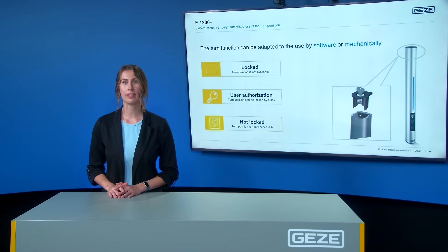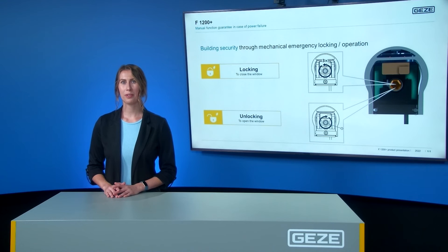If the turn position has been released and is accessible, the button is lit up. Another feature of the F1200 Plus that ensures building security in the event of a power failure is the integrated mechanical emergency locking, also known as emergency operation, designed by a screw inside the drive. Imagine a power outage — the windows are open and it's pouring rain. With the F1200 Plus, you can easily and quickly lock or close the windows with an Allen key and three turns counter-clockwise. It is also possible to unlock or open the window by turning the screw clockwise.